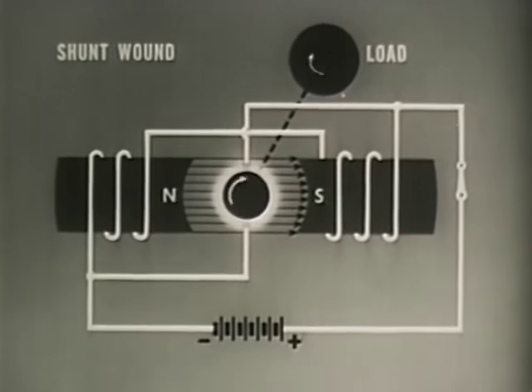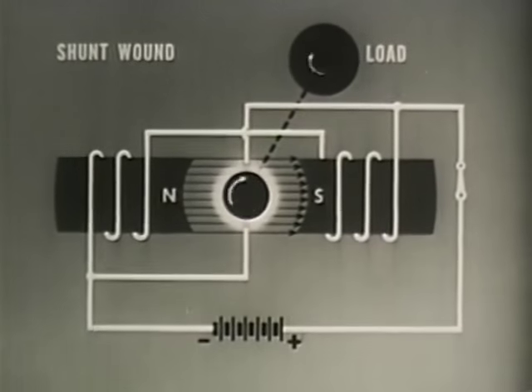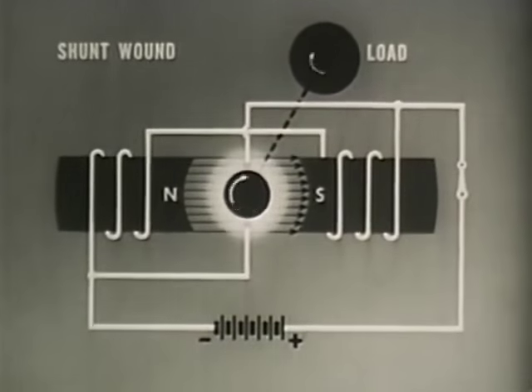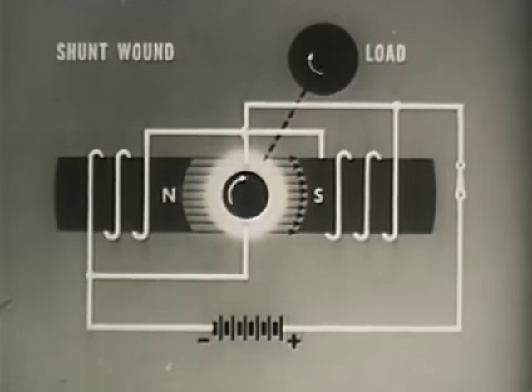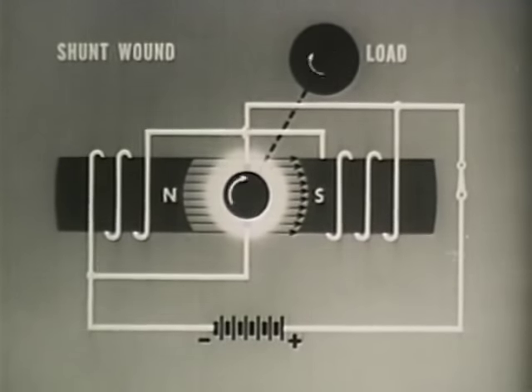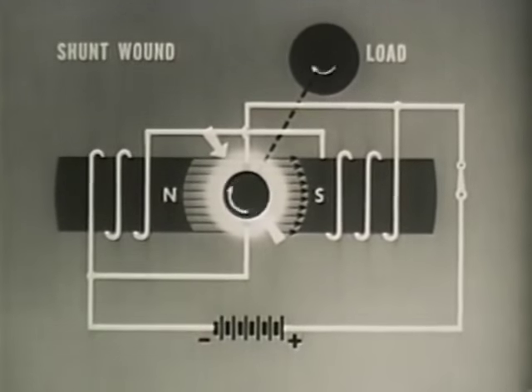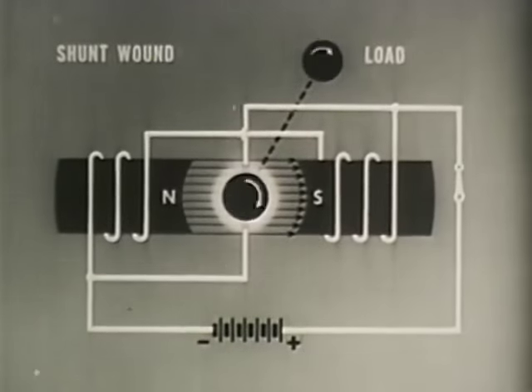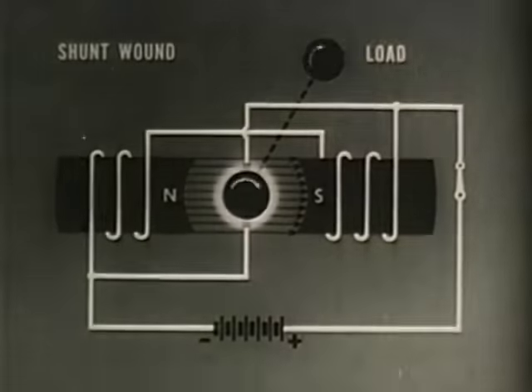In the shunt wound motor, the field coils are connected in parallel directly across the DC input terminals. As more load is applied, the speed of the armature decreases, decreasing the CEMF and increasing the current input. The increase in current input boosts the coupling between the field and armature, increasing the torque and causing the motor to resume approximate running speed. A sudden reduction in load will not damage the motor because the field current is independent of rotor current in the shunt wound motor.